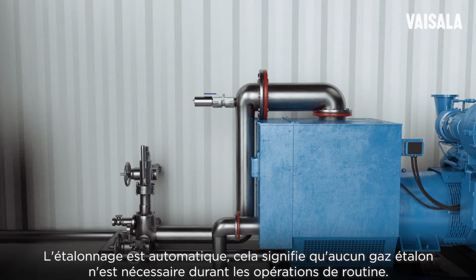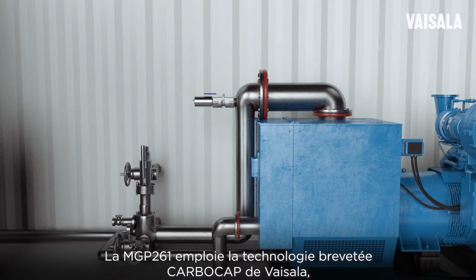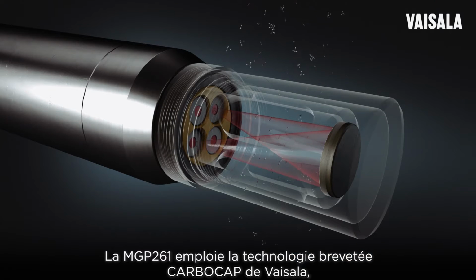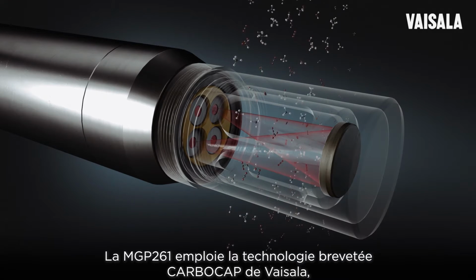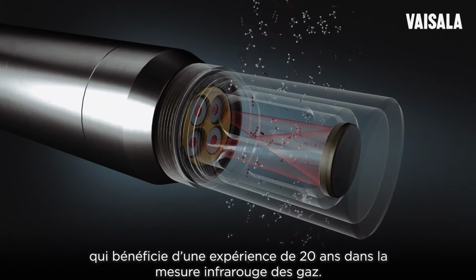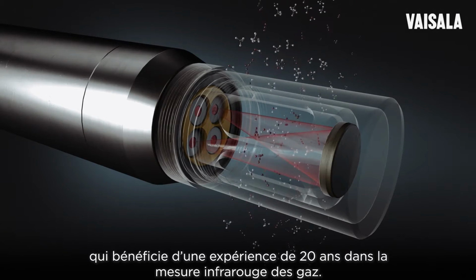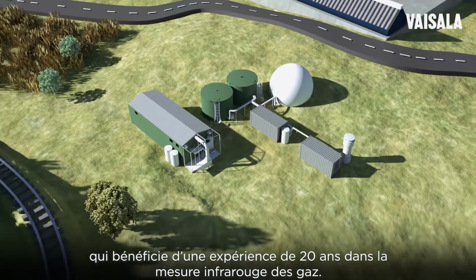Calibration is automatic, meaning no calibration gases are needed in routine operation. The MGP-261 is based on Vaisala's patented CarboCap technology, which boasts a successful 20-year track record in infrared gas measurement.